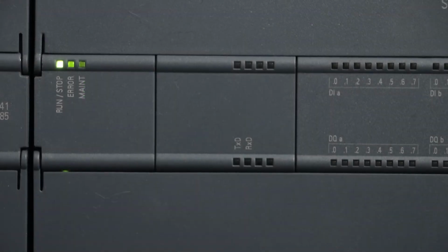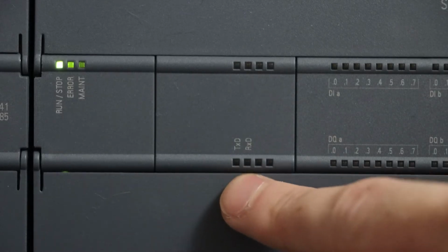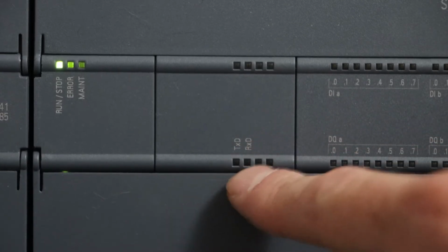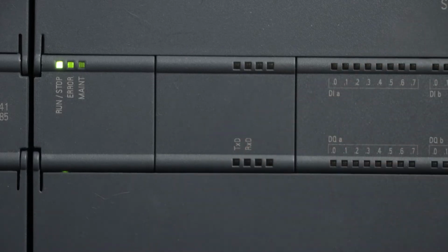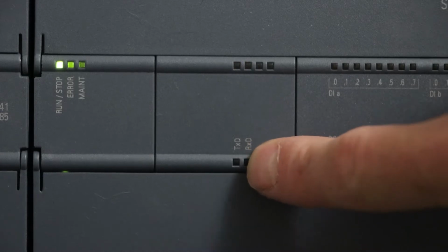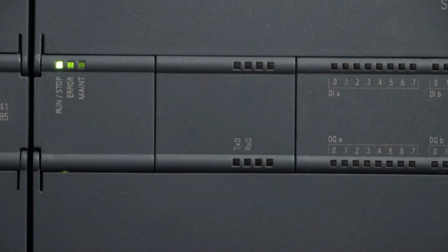So here we are at the PLC. You can see we're only lighting up the transmission light. Now in a very nice feature from Siemens, the light between these lights can actually leak between the two, so it's not abundantly clear sometimes, but we're only firing out requests. We're not getting anything back on the receive. So this is just firing out once a second just to try and see what's out there. Obviously, there is no sensor at that address, so we're just shouting into the void at the moment. But still no error codes coming up on the PLC.